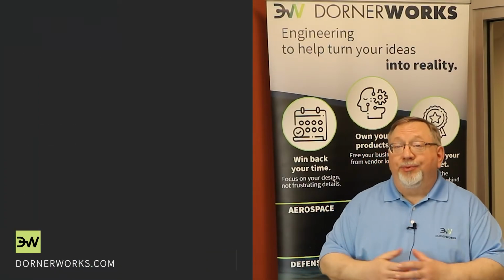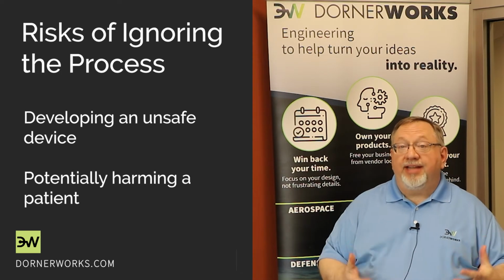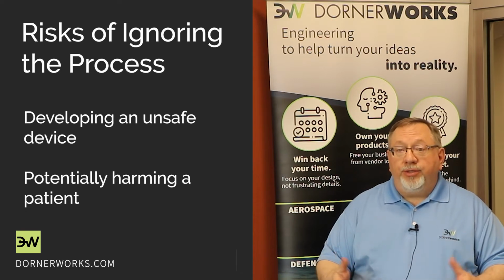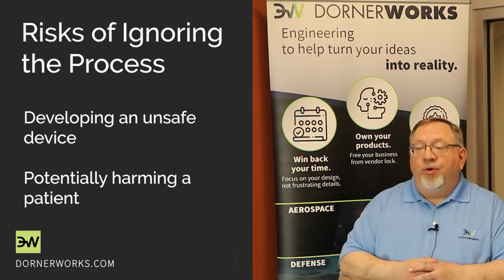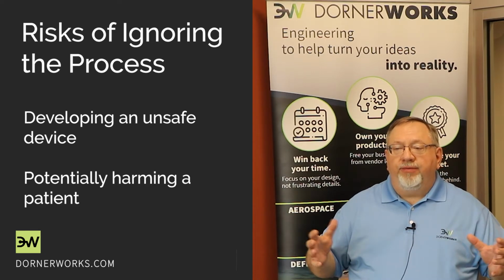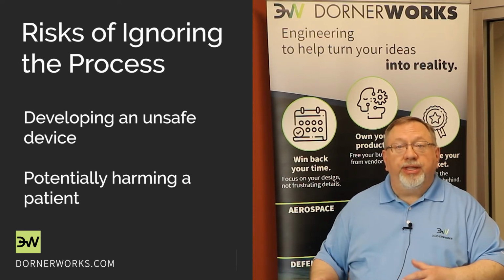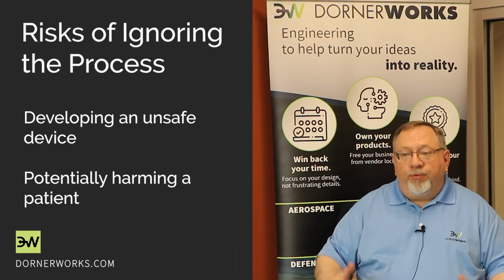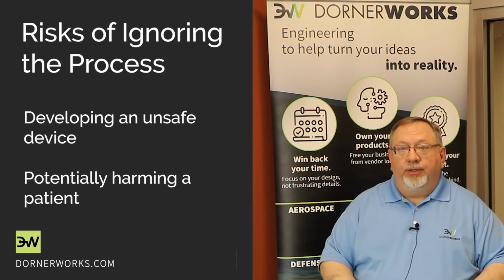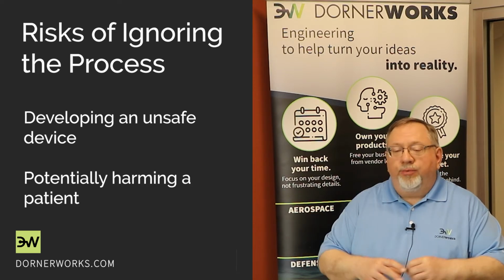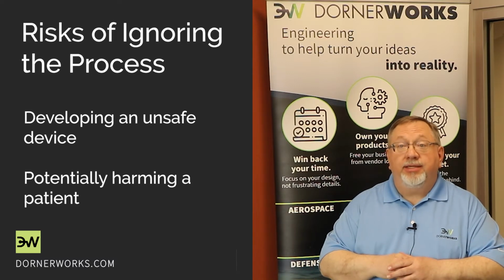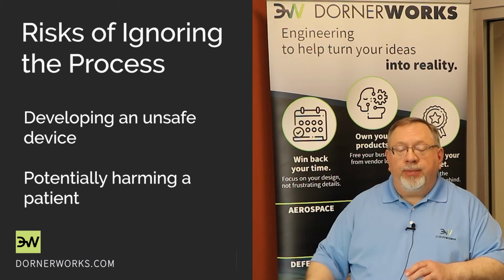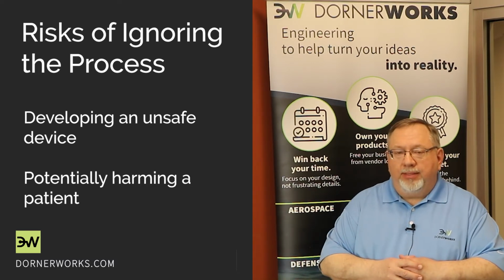What are the risks of ignoring this development process? Well, one of the most obvious risks of not following the process is developing an unsafe and ineffective device that could harm the patients. We don't want to harm the patient. We don't want to harm the operator. So the entire medical device development process is a risk-based approach that looks at signs of potential harm and performs mitigations that then lower the level of harm. Once the risk level has been satisfied, that tells us exactly what processes to what level of detail we need to do. How we do that, that's a separate matter.